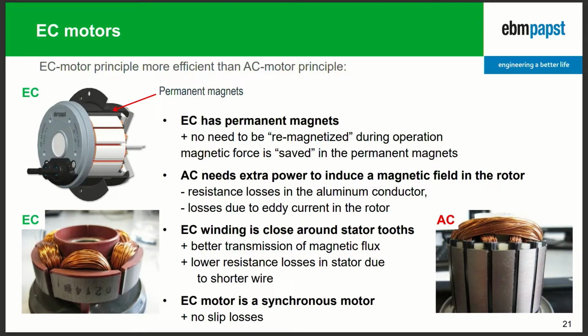to create torque, but the current has to go through. So current through copper, everybody knows, resistance, losses. It generates heat, which you have to get rid of. So therefore, here also we see some percentage points where the EC motor has an advantage. And last but not least, the EC motor is a synchronous motor. That means it's running synchronously with the mains speed. So 50 hertz, 4-pole means 1500 RPM. An AC motor rotates, depending on the power, at something about 1400 RPM. And this also creates losses.